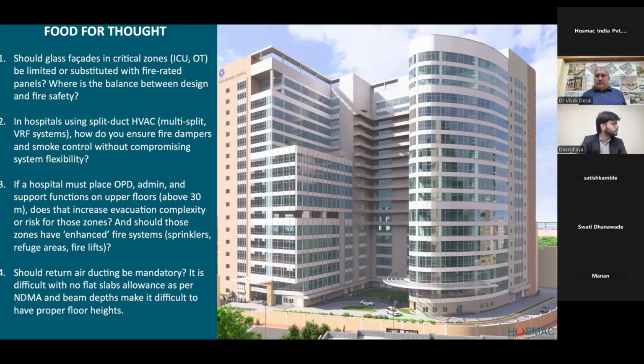It should be discretionary actually, because if you have return ducting for each and every department and sector, then definitely there will be more congestion above the false ceiling. So what we normally do for a hospital, for critical areas like OTs and ICUs, we try to put in a return air duct, and the rest of the areas will be above the false ceiling. On the other hand, from a safety perspective, we also have a smoke exhaust and a fresh air makeup system, and also the fire dampers. So it normally will not matter if we don't provide return air ducts everywhere.